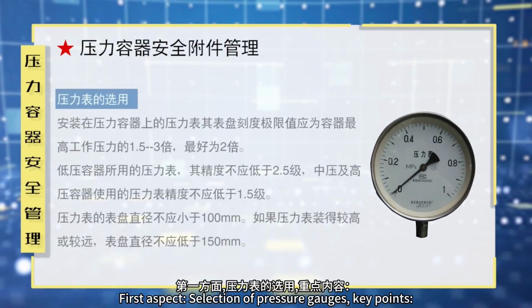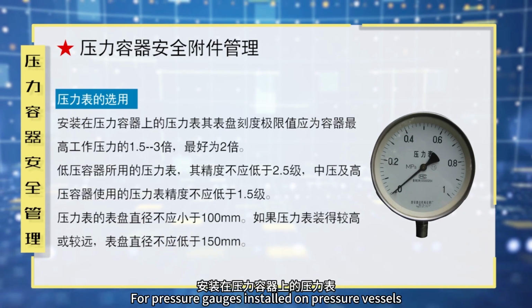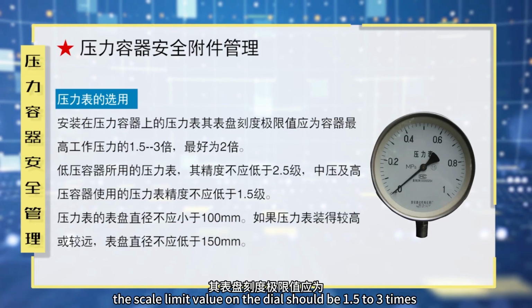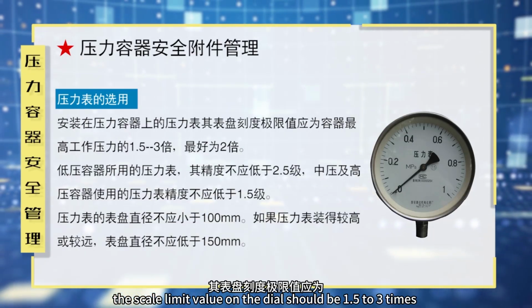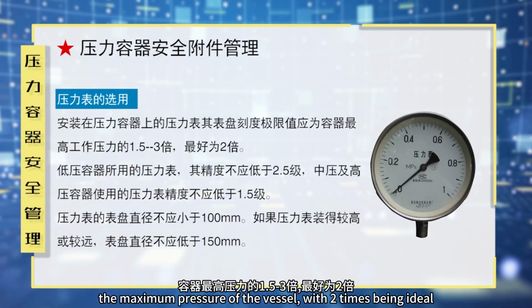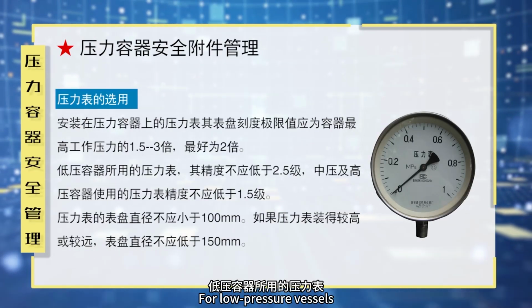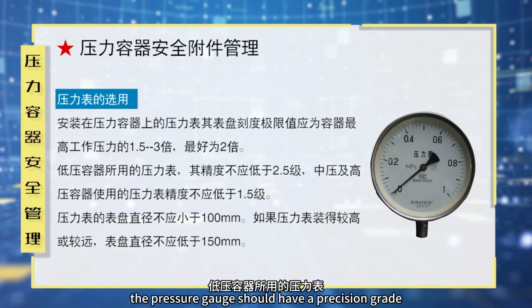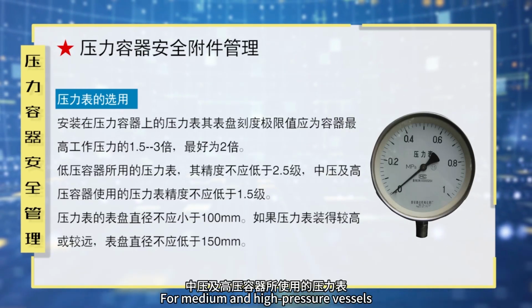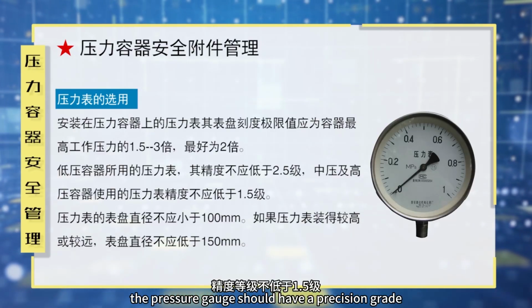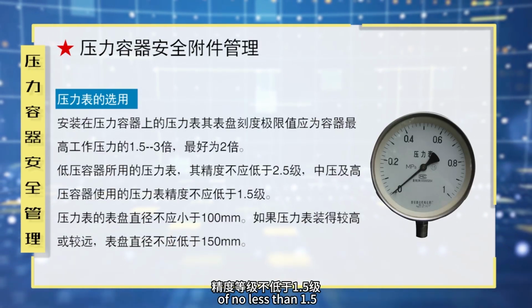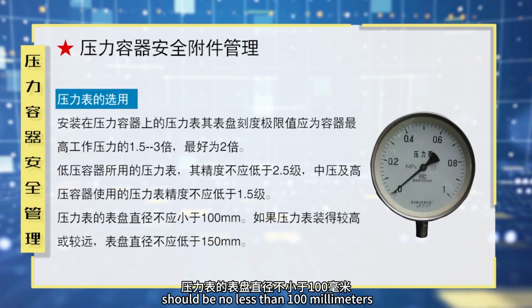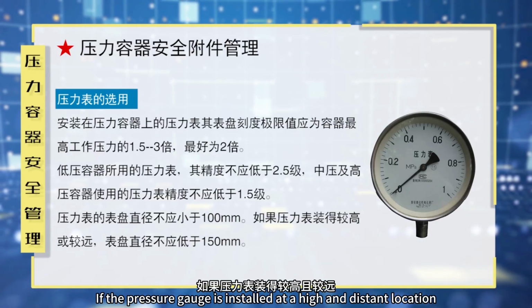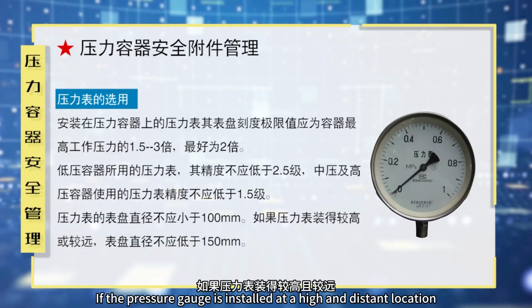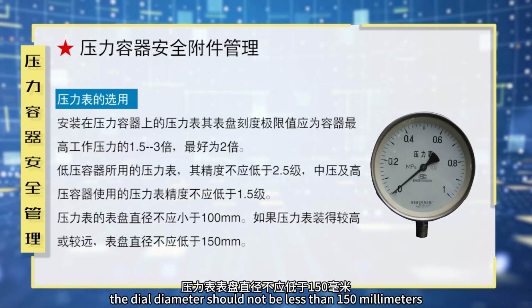First aspect, selection of pressure gauges, key points. For pressure gauges installed on pressure vessels, the scale limit value on the dial should be 1.5 to 3 times the maximum pressure of the vessel, with 2 times being ideal. For low-pressure vessels, the pressure gauge should have a precision grade of no less than 2.5. For medium and high-pressure vessels, the pressure gauge should have a precision grade of no less than 1.5. The dial diameter of the pressure gauge should be no less than 100 millimeters. If the pressure gauge is installed at a high and distant location, the dial diameter should not be less than 150 millimeters.